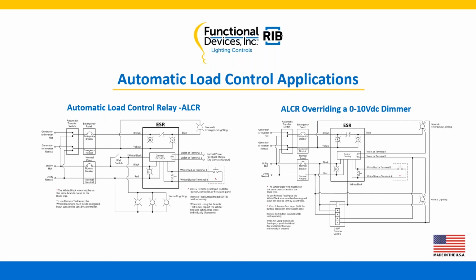What's actually happening at the top, when normal power drops off the bottom, that light goes out. What happens is that ATS switches over, we create the path for that emergency power to get to that emergency light. You see the violet, as I mentioned in the earlier diagram, you see the two violet colors. What's happening there is that is your 0 through 10 volt dimming going through there. So what we do, we break that circuit with that contact inside there, and that allows that normal emergency light to go to full brightness, as code says it has to.